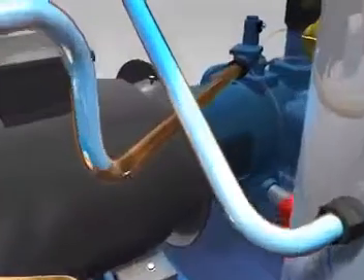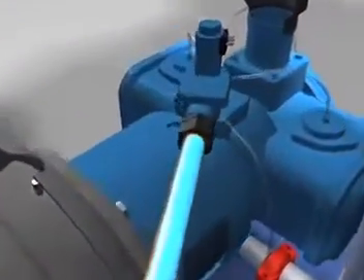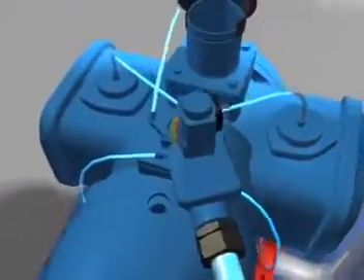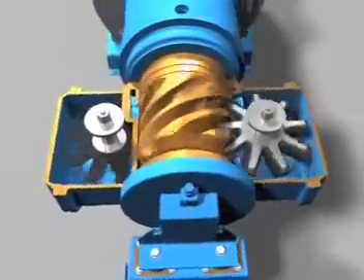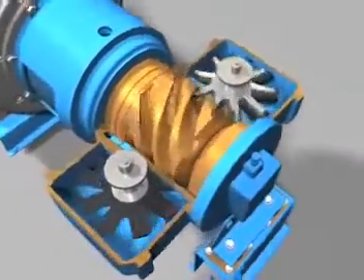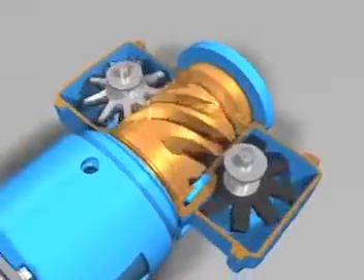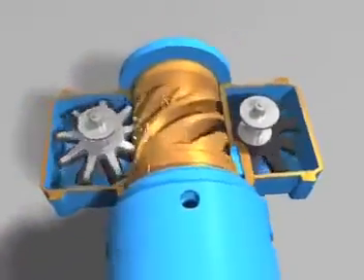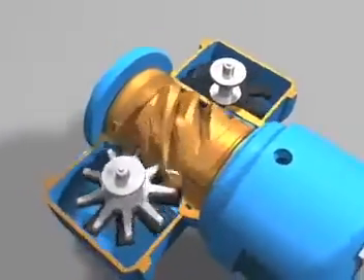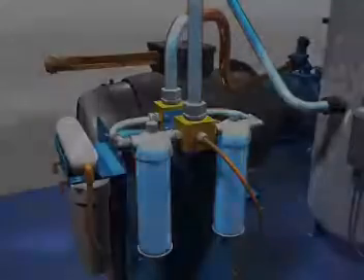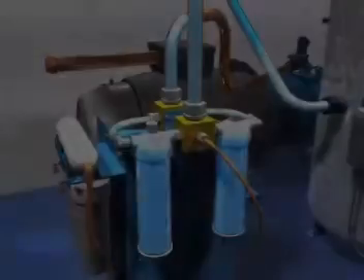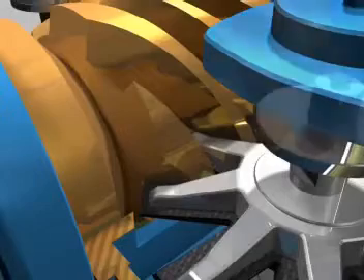The excellent cooling features of water injection enable the compressor to operate at a low temperature, so near isothermal compression is achieved. The unique construction of the air end ensures the compressor runs with particularly low vibration and minimized bearing loads, reducing energy consumption and ensuring a long life. As it is a simple construction with few moving parts, maintenance is significantly reduced.